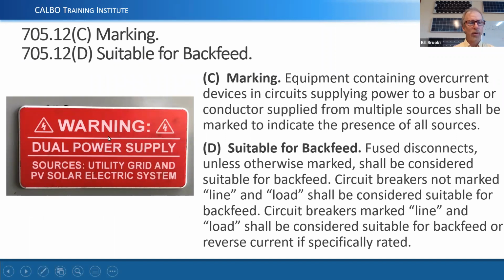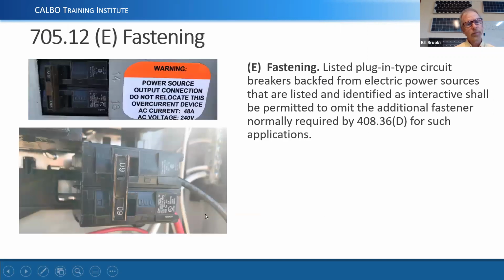Marking: if we have a panel board that has more than one source of supply, then we have to identify what sources of supply are there. If we're going to backfeed circuit breakers, then they cannot be marked line and load, because generally line and load marked circuit breakers are designed for power flow in one direction.